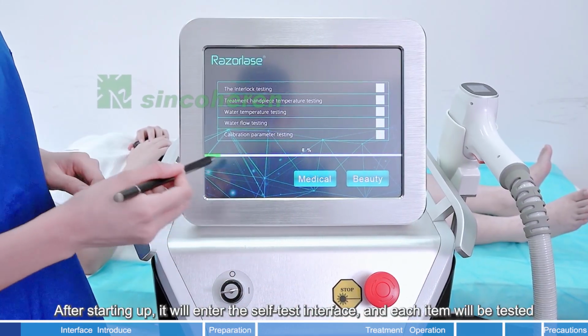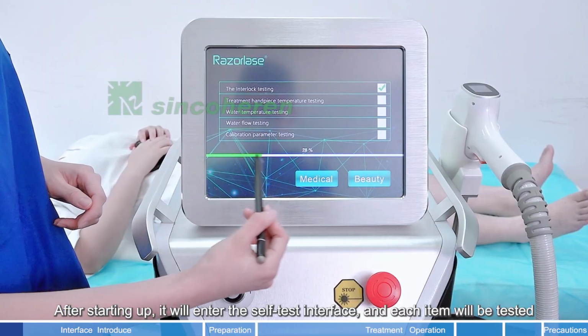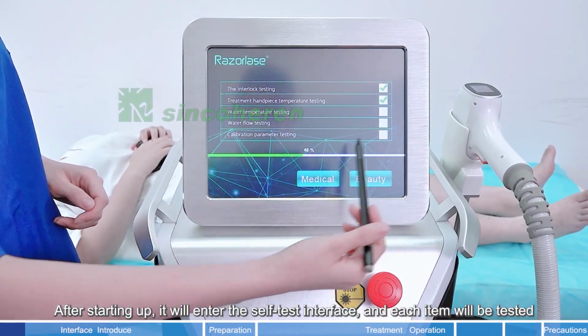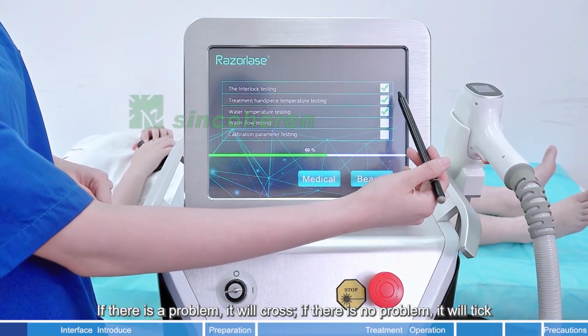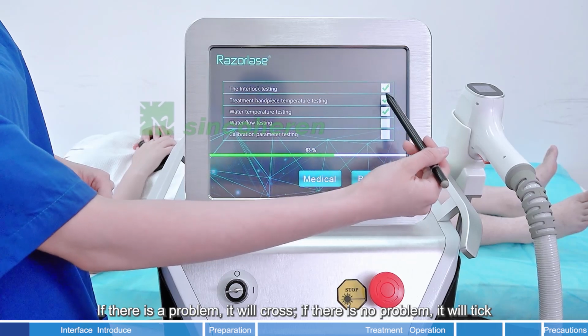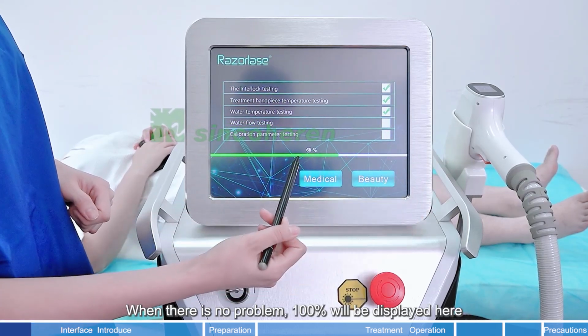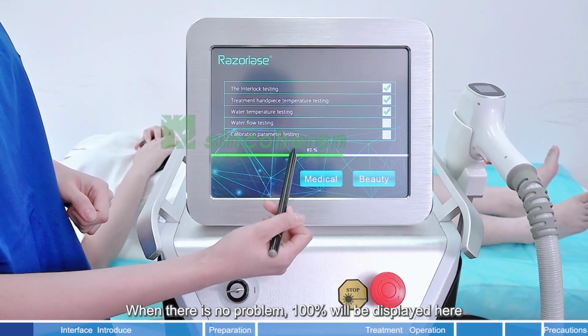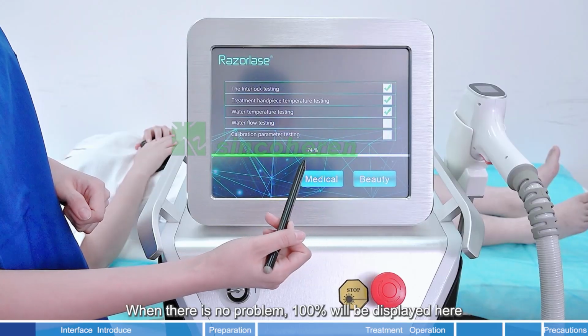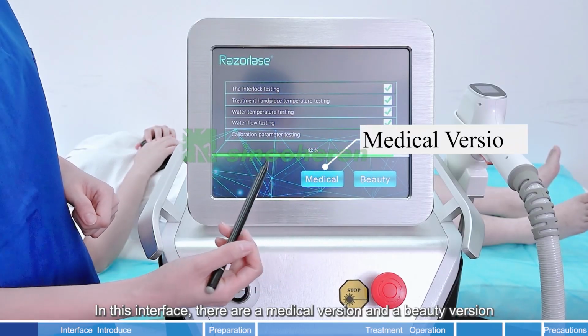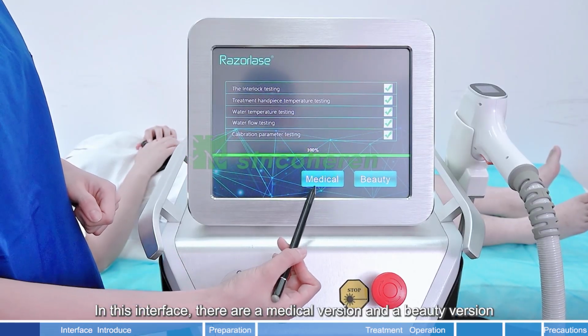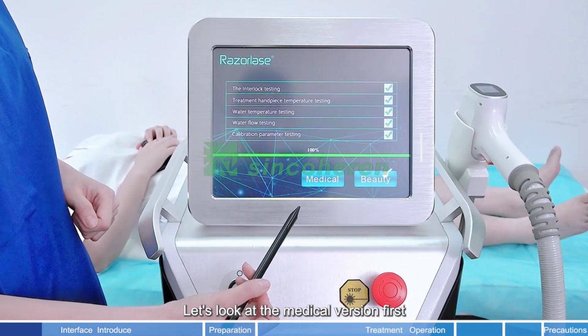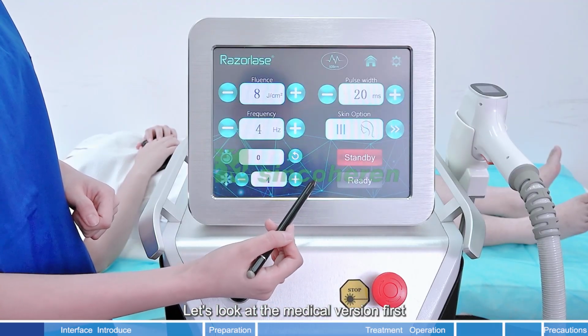After starting up, it will enter the self-test interface, and each item will be tested. If there is a problem, it will cross. If there is no problem, it will tick. When there is no problem, 100% will be displayed here. In this interface, there are a medical version and a beauty version. Let's look at the medical version first.